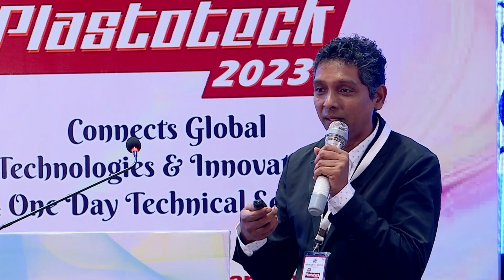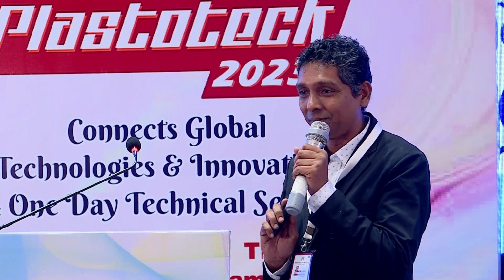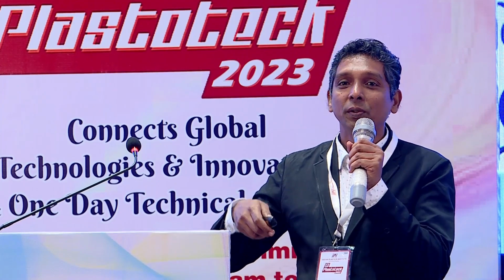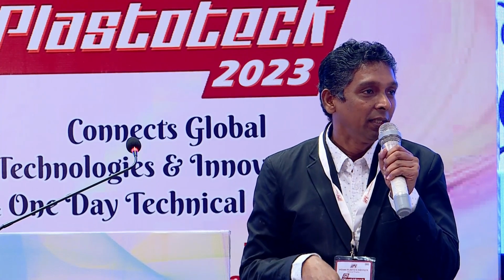Whether we are going with 2 machines or 10 machines or 100 machines, the design approach is the same. Maybe the flow may increase, but the calculation is also the same. For every bend, every tee, every tee-through flow, we should calculate the pressure drop properly. Then only can we select the proper pump. If you are not selecting the proper pipe size and not calculating the proper pressure drop, you are unable to select the proper pumping head. If you are not selecting the proper pumping head, you will not get the flow and pressure till the end of the machines.